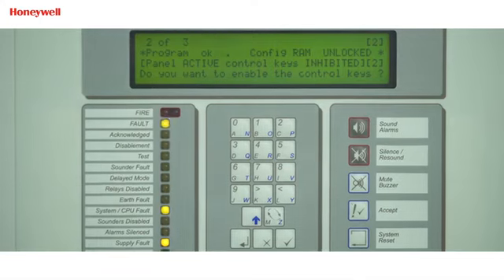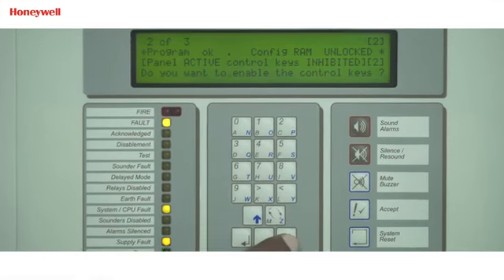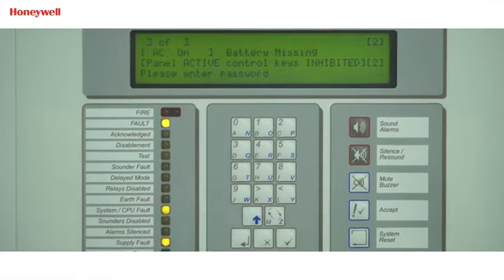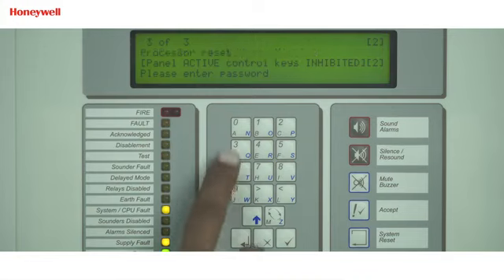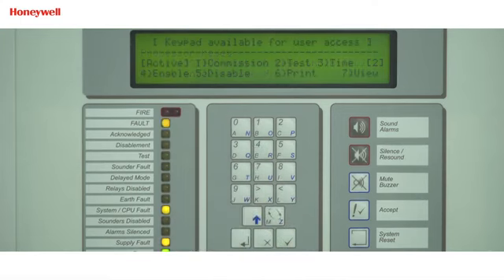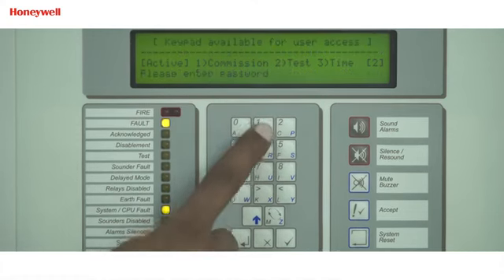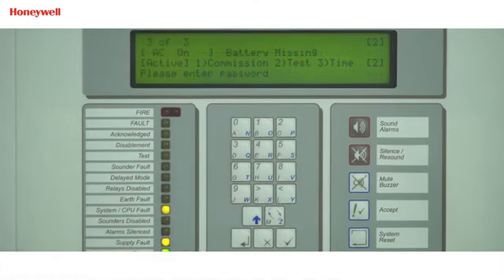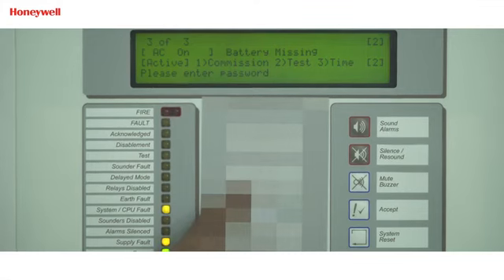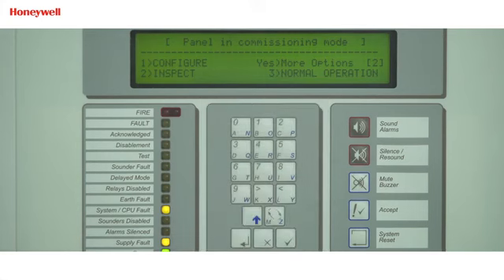First, to enable level 2 operation, press the tick mark button and the display will prompt for entry of the level 2 password. Enter the level 2 password using the numeric keys. The display then shows the main menu of user options. To access the commissioning function in the panel, press 1 to select the commissioning option. The display will prompt for entry of the level 3 password. Enter the level 3 password using the numeric keys. The display will then show the commissioning menu options.